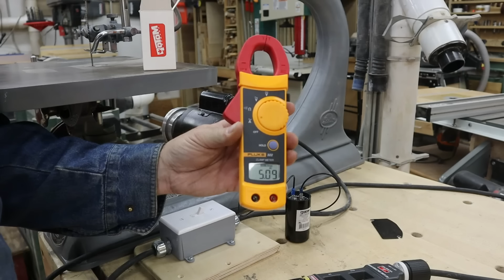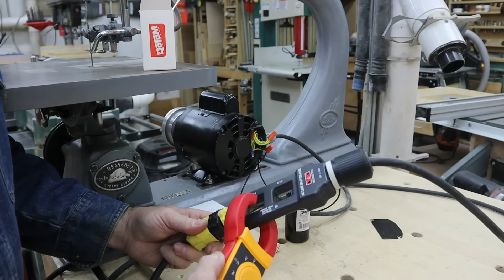Now before I turn anything on, we can still see the previous reading in the memory of my ammeter. I'm going to go ahead and erase it. So we had a previous reading of 5.09 amperes. Now let's turn on the power and we're going to get a new reading. In theory I should have eliminated an awful lot of that unwanted current, and look at this, I'm actually reading about 2.1 amperes. So let's hit the memory function.